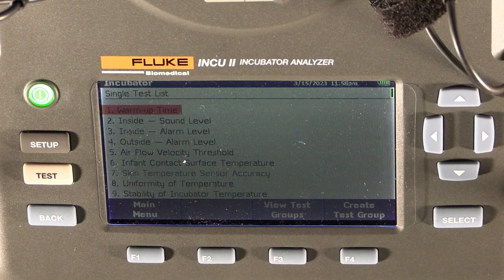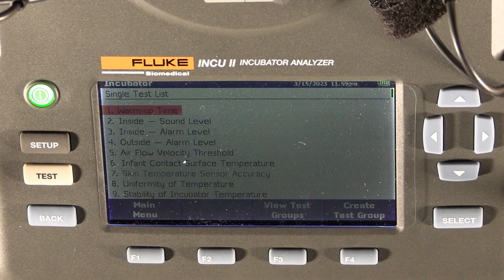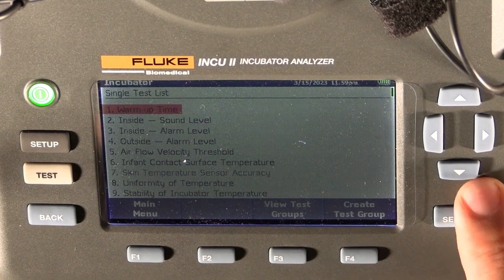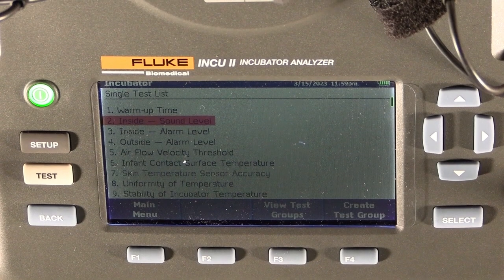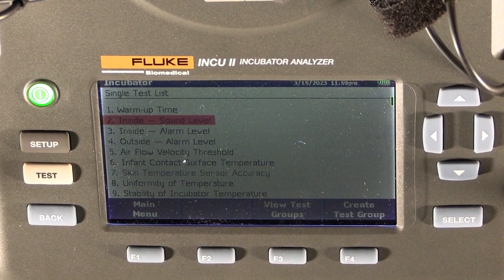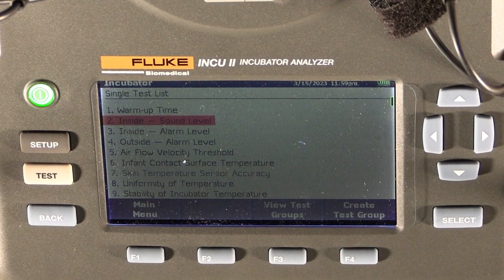What we're measuring here is the time it takes this incubator from startup to the time where it reaches stability on temperature. So we want to know from startup how long it takes until it stabilizes. The second one is our inside sound level. For that, we make use of a microphone inside the unit, which will measure for us in decibels the sound coming from the fan motors inside the unit to determine whether that is a comfortable environment for the baby.